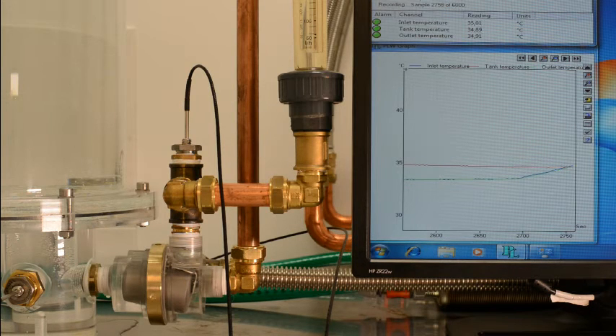From this point on the valve can start moving to the open position, but this particular valve actually has a slight bias towards closing off the tank to make sure that there is never any heat withdrawn from the system, and so a small offset of a couple of tenths of degrees, up to a degree, is required for the valve to actually move to the open position.